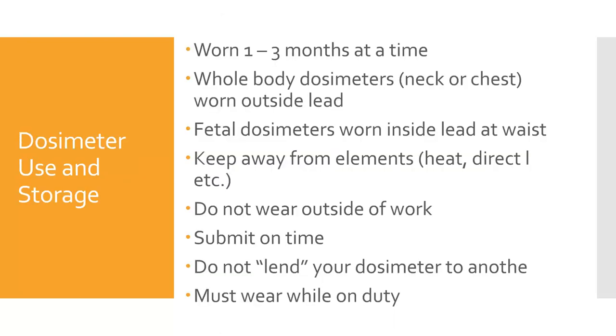Personal dosimetry devices are most limited by improper use, so it is important to be mindful of placement, storage, and care of your dosimeter. Dosimeters must be worn as designed — become familiar with the manufacturer's recommendations. Most dosimeters are worn for a period of one to three months. Whole body dosimeters must be worn at neck or chest level. Your dosimeter should be worn on the outside of your lead apparel unless specified. For example, fetal dosimeters are meant to be worn on the inside of the lead apron at waist level.